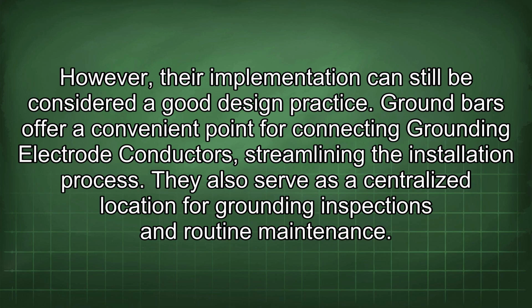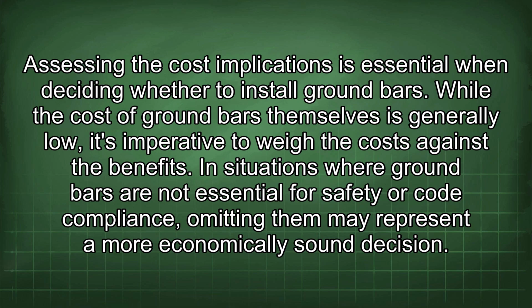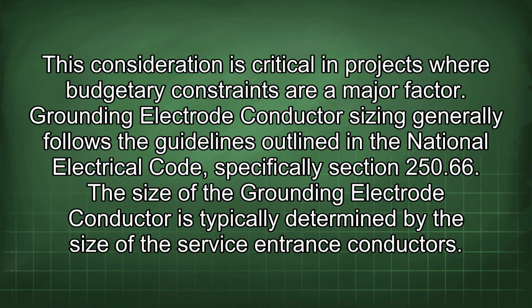Ground bars offer a convenient point for connecting grounding electrode conductors, streamlining the installation process. They also serve as a centralized location for grounding inspections and routine maintenance. Assessing the cost implications is essential when deciding whether to install ground bars. While the cost of ground bars themselves is generally low, it's imperative to weigh the costs against the benefits. In situations where ground bars are not essential for safety or code compliance, omitting them may represent a more economically sound decision. This consideration is critical in projects where budgetary constraints are a major factor.